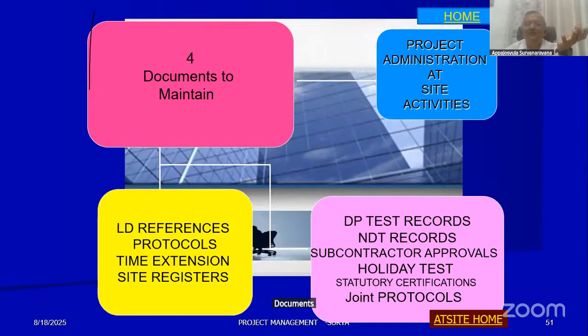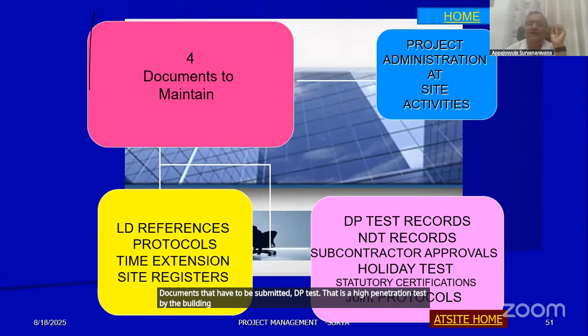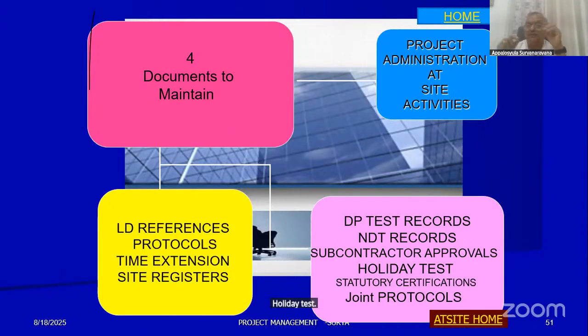Documents that have to be submitted include DP test - dye penetration test for welding, radiography test, and holiday test. Holiday test checks whether coating is properly applied. If there's any gap in the coating, that's a 'holiday' - a gap. The instrument will give an indication, then it has to be peeled out and recoated, and tested again.